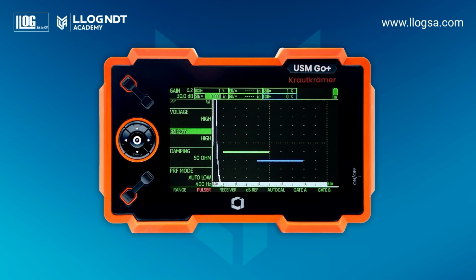Voltage and energy set to high. Damping at 50 ohms. The pulse repetition frequency set to auto high. We select the frequency of the probe to be used. If the frequency is unknown, we can use broadband. For this example, we will use a 5 MHz probe. For wave rectification, we select full. Dual mode, off. Reject at 0%, and then we move to the Gate A submenu, where we set the gate height at 20%. And the measurement mode to peak.